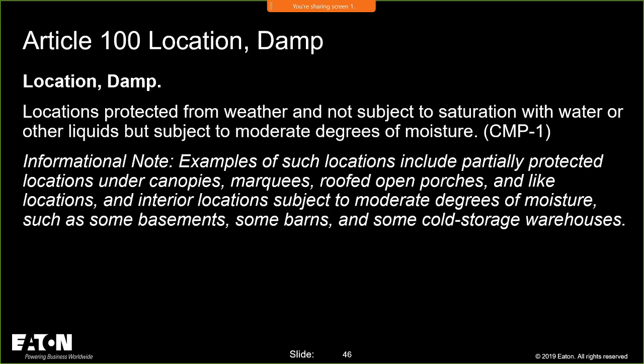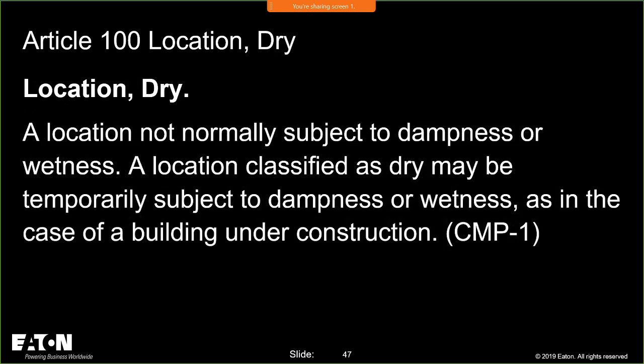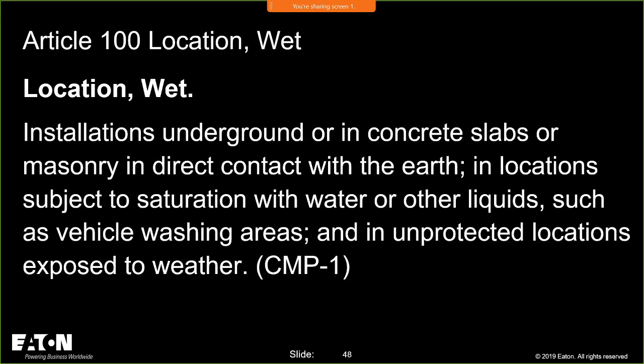You have to understand what a damp location is: protected from weather, not subject to saturation with water or other liquids. A dry location is not normally subject to dampness or wetness. And a wet location is underground or in concrete slabs within the earth, in locations subject to saturation by water, outside, all the unprotected areas.